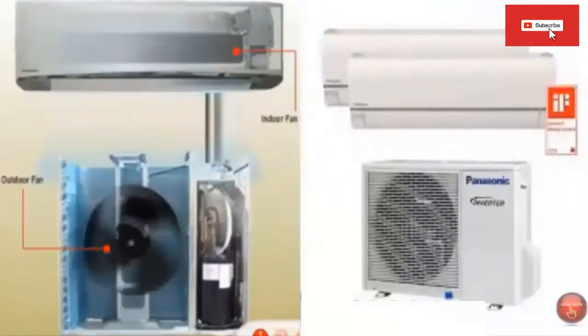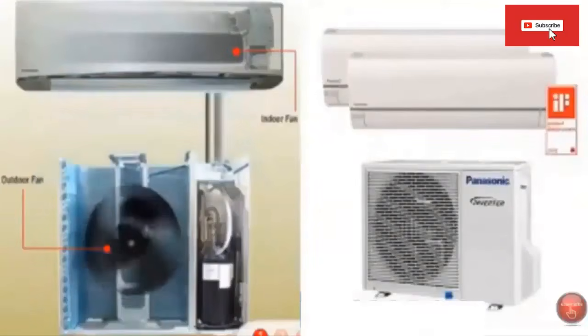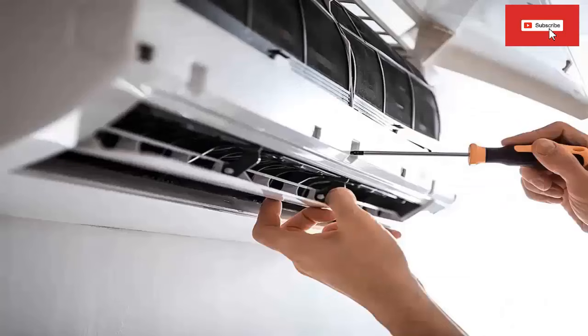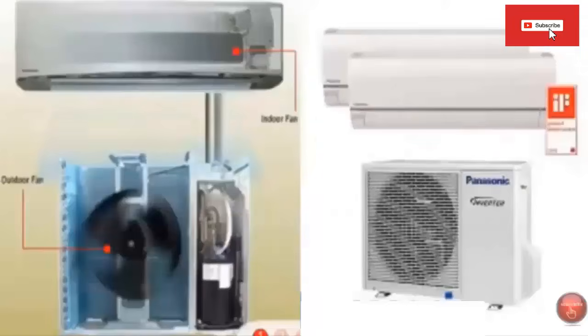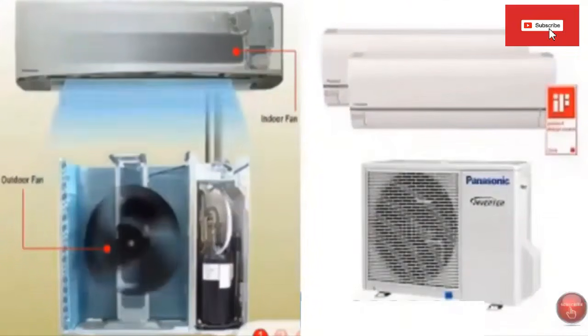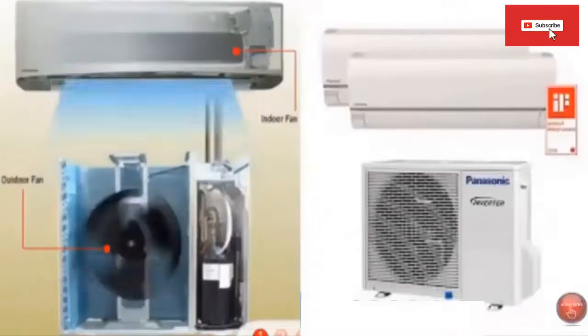However, in some brands, error 1 can be a protection that activates the device so that an existing fault is solved. For example, it could be dirty filters, lack of gas, condensate drainage problems, the fan not starting, or a problem with the supply voltage. So it is a code that can share several meanings. You can follow the general recommendations below to fix a failure related to error 1.